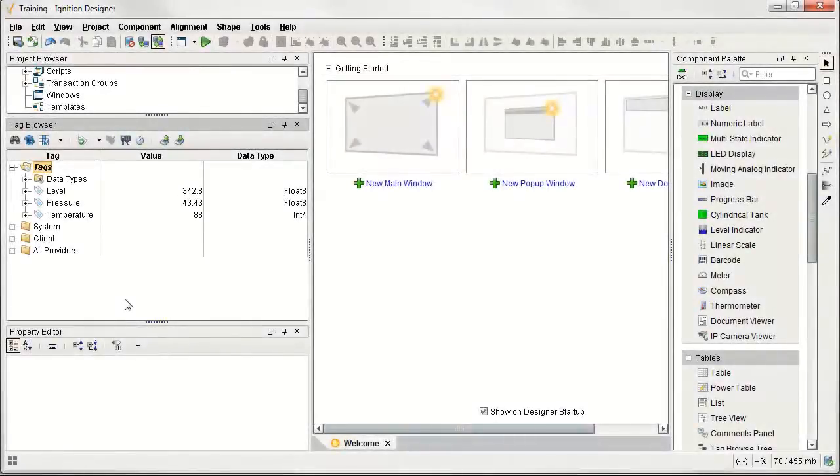There are a lot of people that want to pull tags at certain times of the day. And we can accomplish that in Ignition by using the driven scan class. We can set the condition of the driven scan class to be true at certain times of the day and false at others. So in order to use that scan class, we have to create another tag here in Ignition that's going to drive that condition.